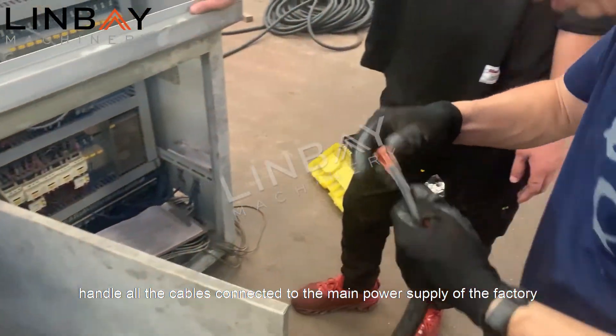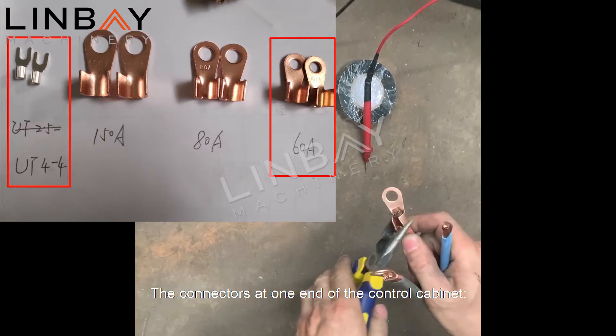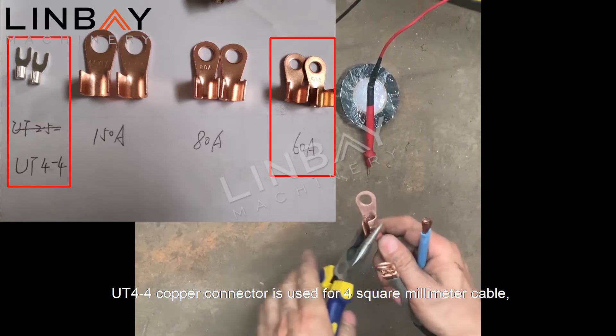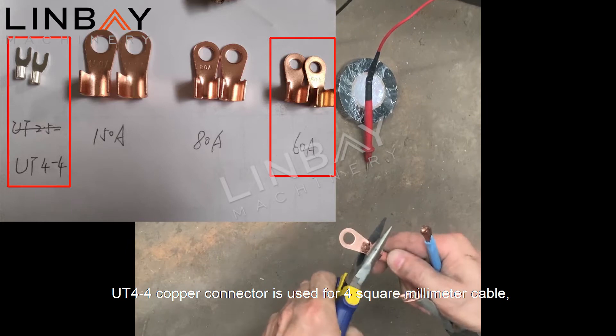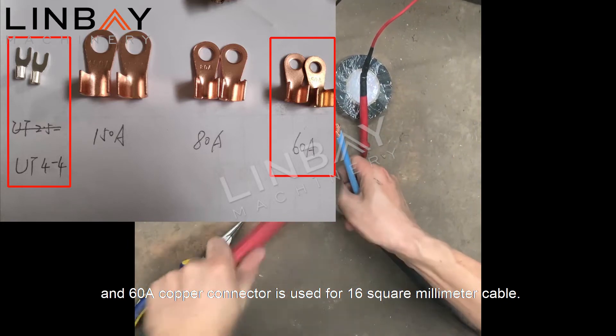The connectors at one end of the control cabinet: a UT4-4 copper connector is used for four square millimeter cable, and a 60A copper connector is used for 16 square millimeter cable. Connectors at one end of the main power box use a 60A to 150A copper connector.